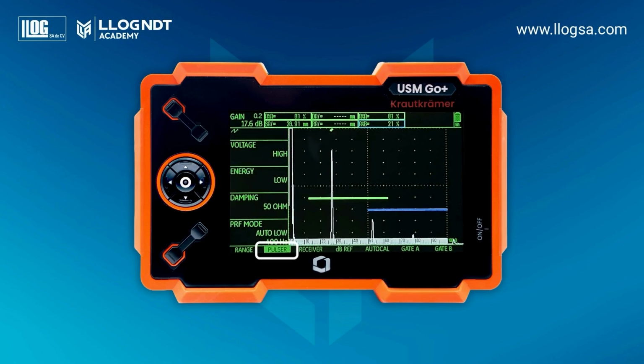The second group contains pulser settings. The pulser voltage is the electrical energy sent to the piezoelectric crystal. It can be set to high or low depending on whether greater penetration is needed in thick or attenuating materials, to improve signal-to-noise ratio, or to increase sensitivity. The next function sets the sound energy to low or high, which affects penetration and resolution.